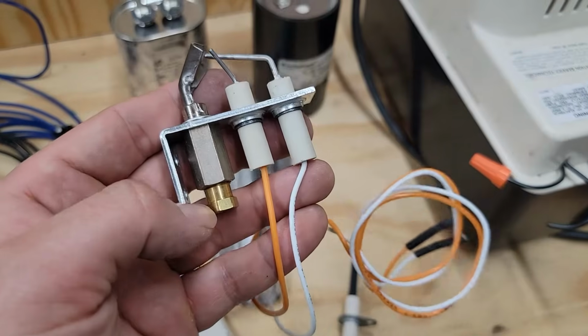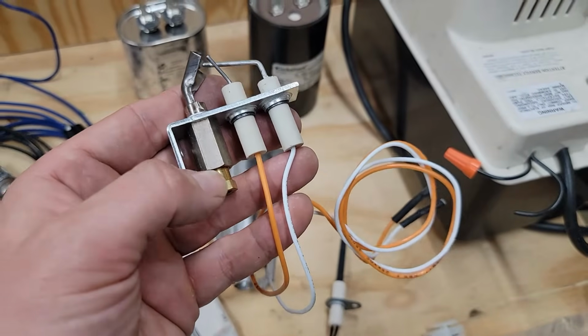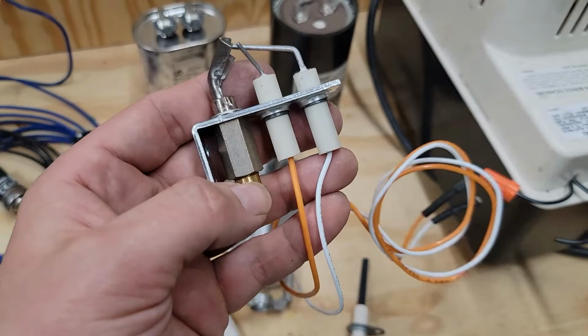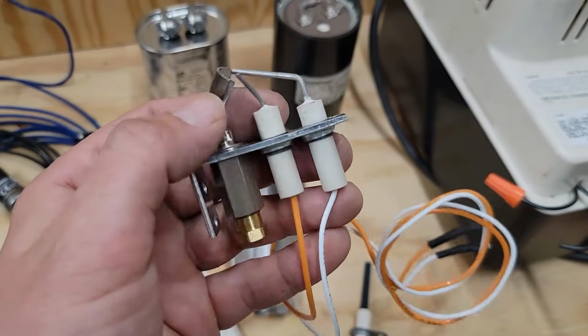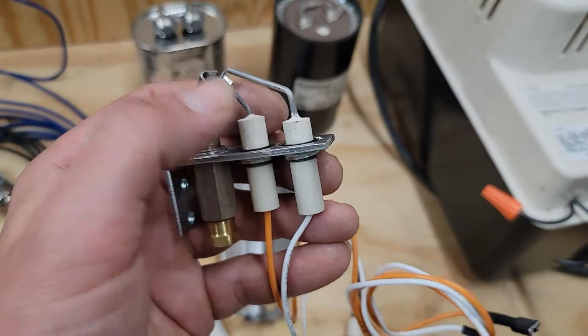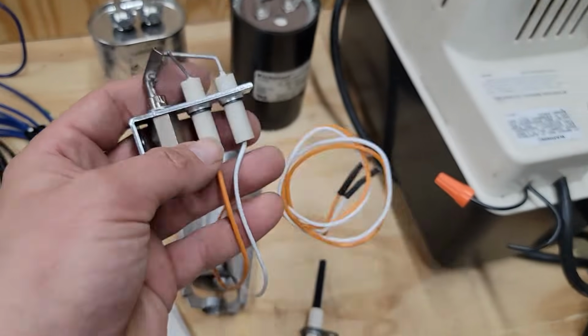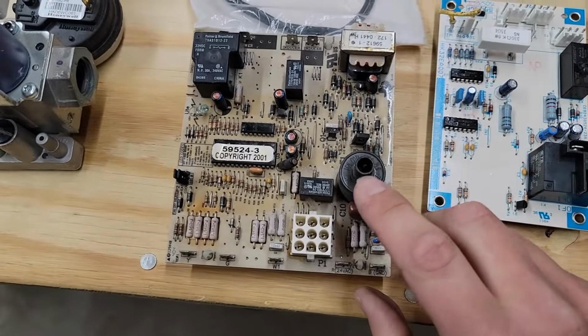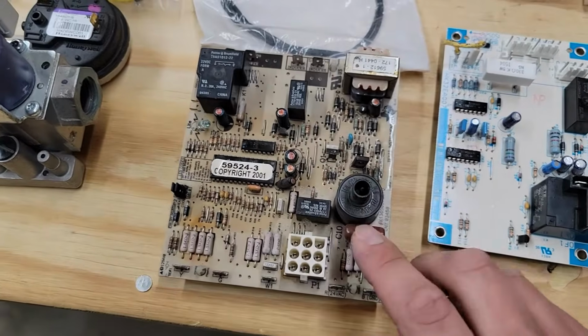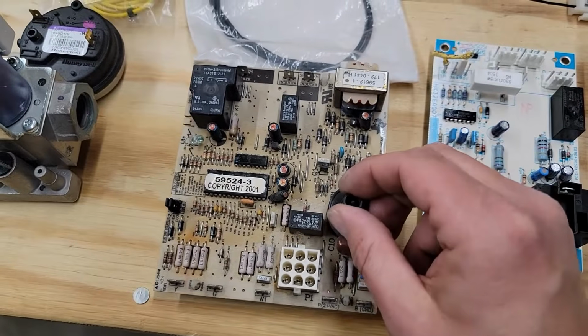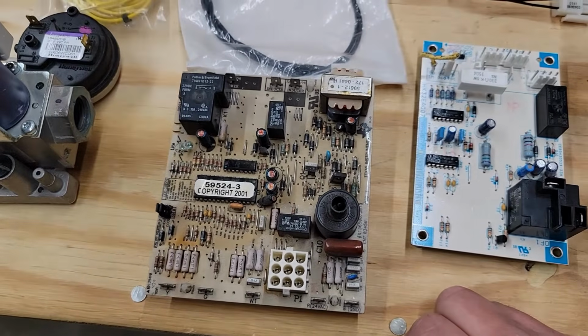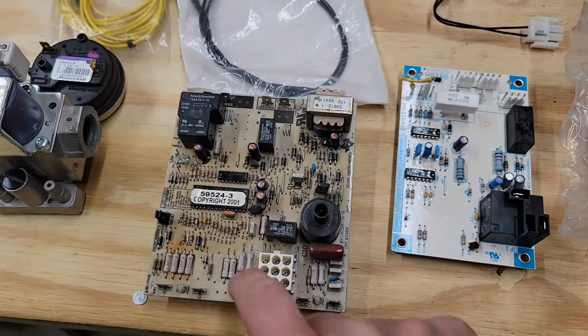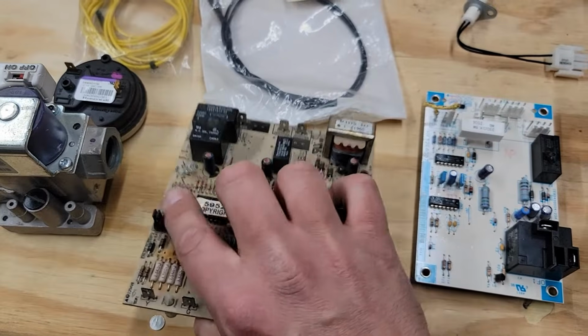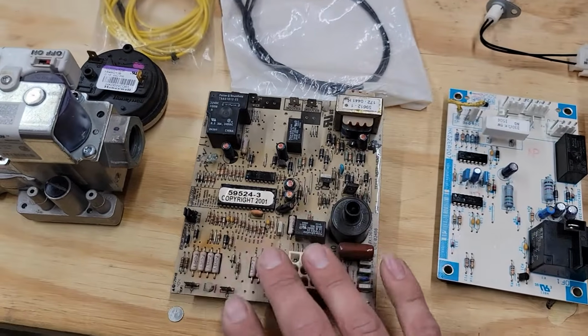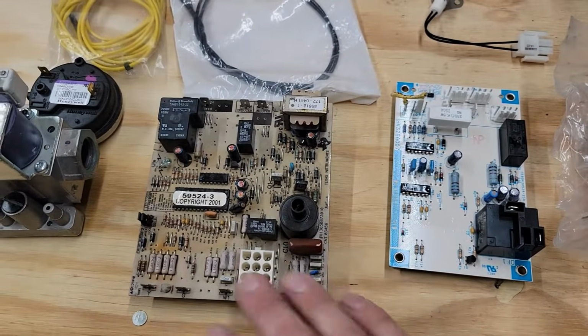Once it sparks and the pilot tube is flowing gas from the gas valve, from the pilot valve into this tube, out here, it sparks, then it ignites, and then the flame sensor sends a signal back to the board, letting the board know, hey, we have flame. This is the ignition control board, and this is where that spark would come from. This right here is the spark igniter. So we also have a wire that comes back to this board. This is the ignition control board, all right? This right here you'll find in a furnace, and this controls the ignition, and then the safeties and all that.